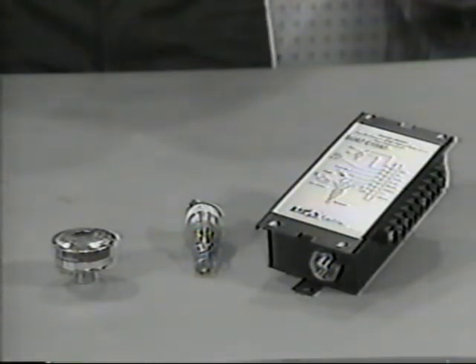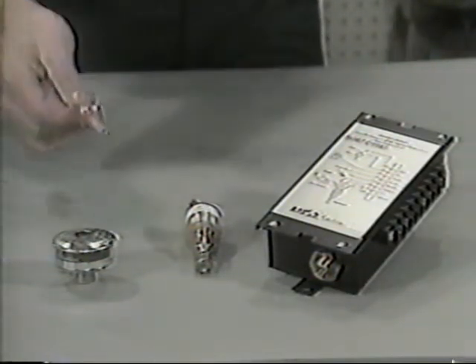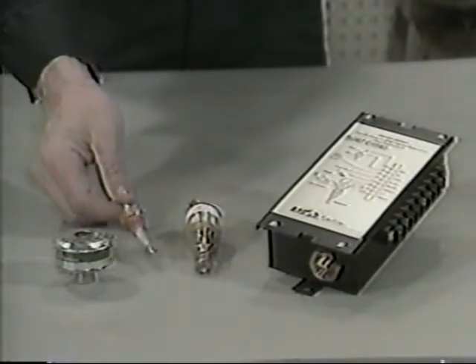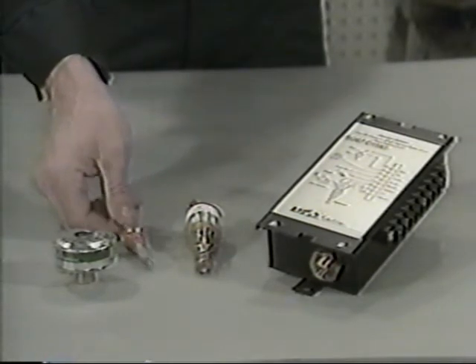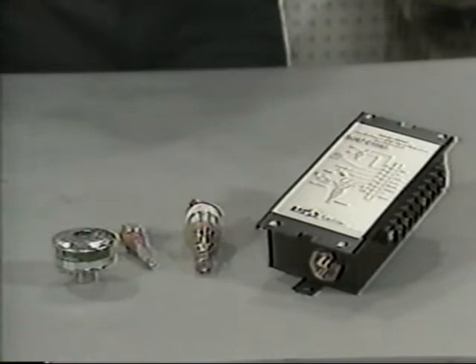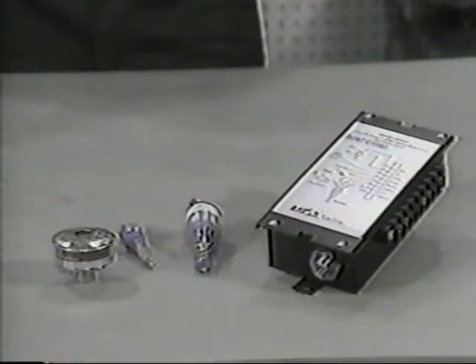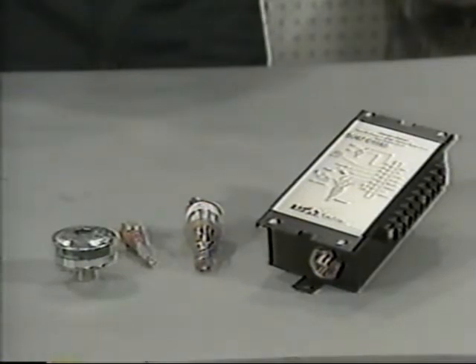9042 is the two-way system, and the kit contains the module, the alarm stat, and the warning device. 9041 is the three-way version, and its kit also contains the low coolant probe, and of course the three-way version of the module. Neither 9042 nor 9041 contains the harness or the installation hardware. These must be supplied by the installer. Let's begin our discussion of system function with a look at the two-way versions.